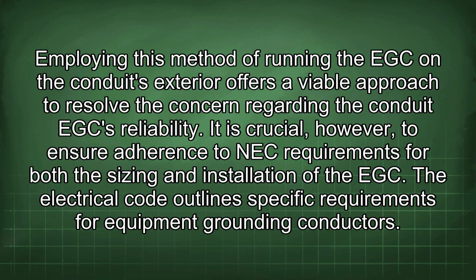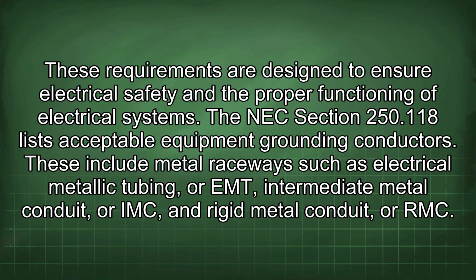Employing this method of running the EGC on the conduit's exterior offers a viable approach to resolve the concern regarding the conduit EGC reliability. It is crucial, however, to ensure adherence to NEC requirements for both the sizing and installation of the EGC. The electrical code outlines specific requirements for equipment grounding conductors. These requirements are designed to ensure electrical safety and the proper functioning of electrical systems.